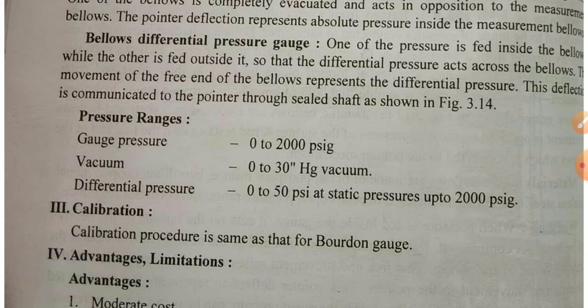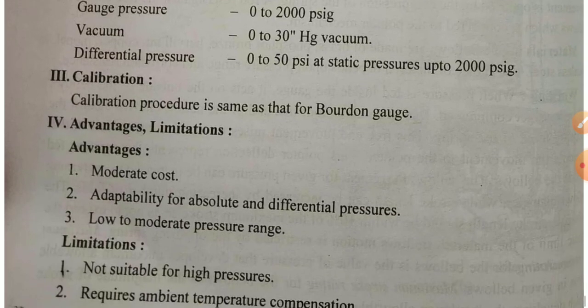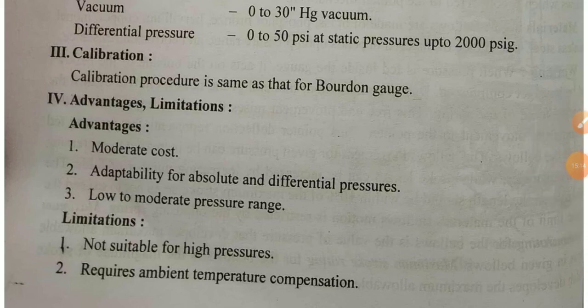Now the last one: the calibration procedure is the same as for the Bourdon gauge. Some advantages: moderate cost, absolute and differential pressure, low to moderate pressure range. Limitations: not suitable for high pressure, requires ambient temperature compensation.